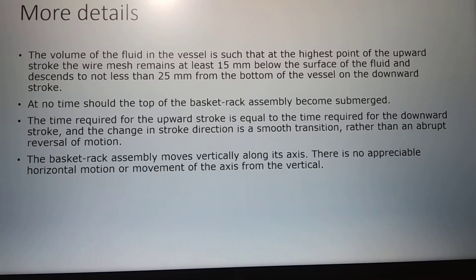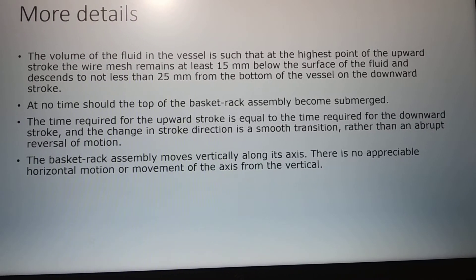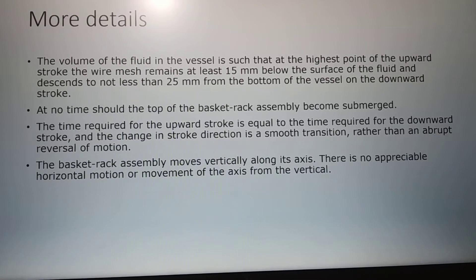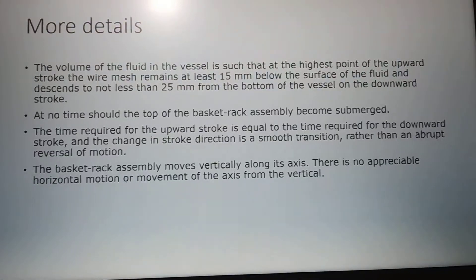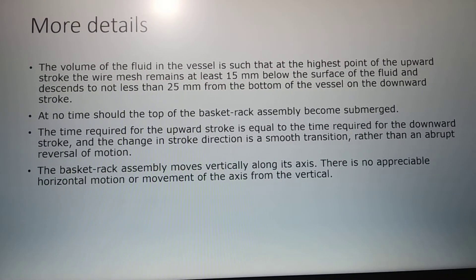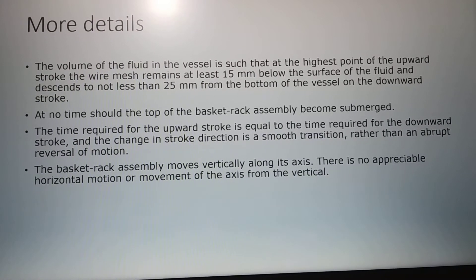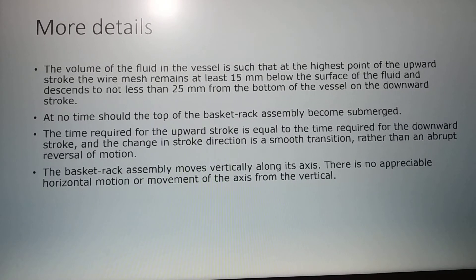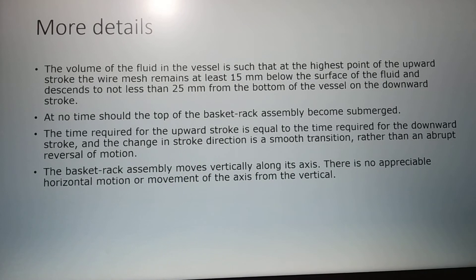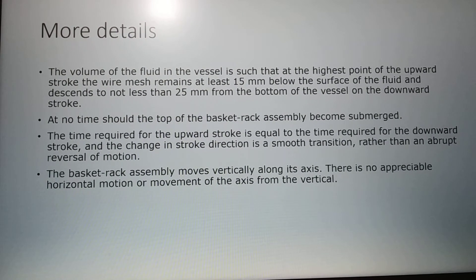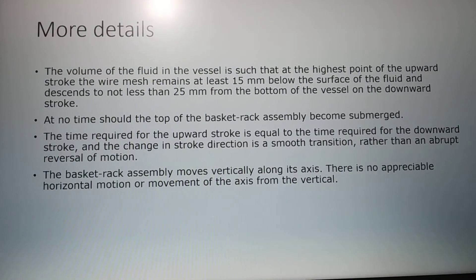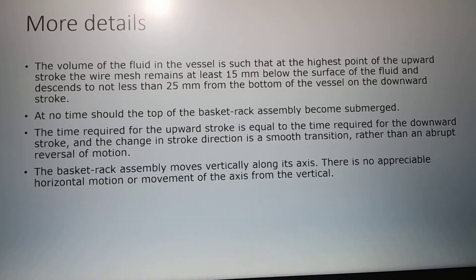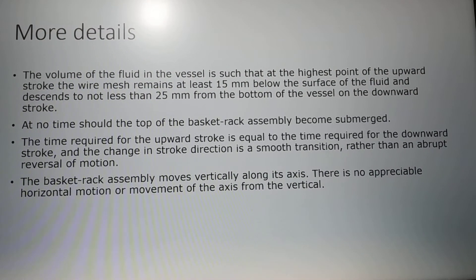The volume of fluid in the vessel should be such that at the highest point of the upward stroke, the wire mesh remains at least 15 mm below the surface of the fluid — in most cases, water. When the basket is at its lowest position, it should be not less than 25 mm from the bottom of the vessel. At no time should the top of the basket rack assembly become submerged, meaning the basket should not be completely deep inside the fluid.